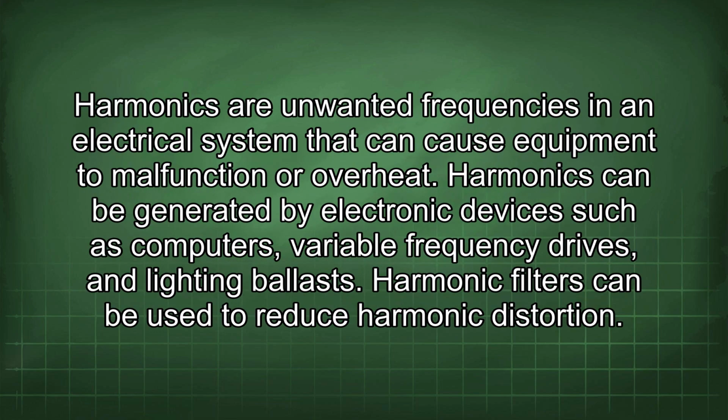Harmonics are unwanted frequencies in an electrical system that can cause equipment to malfunction or overheat. Harmonics can be generated by electronic devices such as computers, variable frequency drives, and lighting ballasts. Harmonic filters can be used to reduce harmonic distortion.